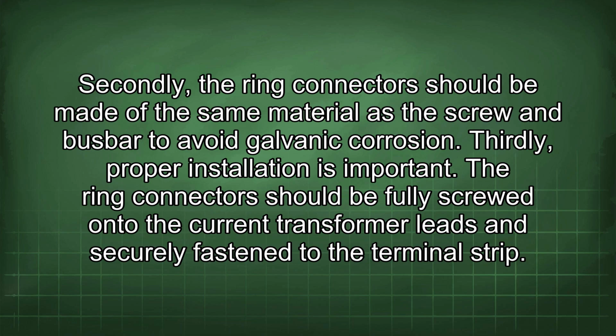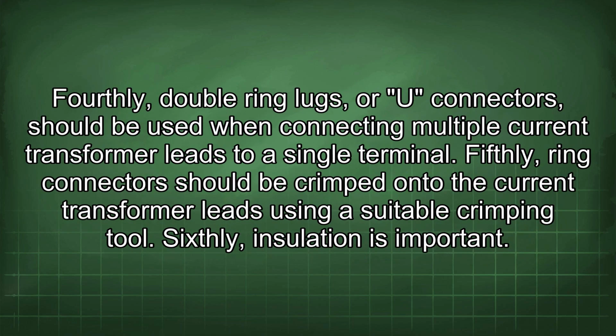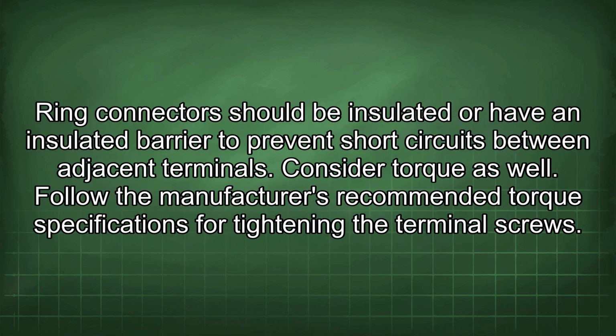The ring connector should be fully screwed onto the current transformer leads and securely fastened to the terminal strip. Fourthly, double ring lugs, or U-connectors, should be used when connecting multiple current transformer leads to a single terminal. Fifthly, ring connectors should be crimped onto the current transformer leads using a suitable crimping tool. Sixthly, insulation is important. Ring connectors should be insulated or have an insulated barrier to prevent short circuits between adjacent terminals. Consider torque as well.